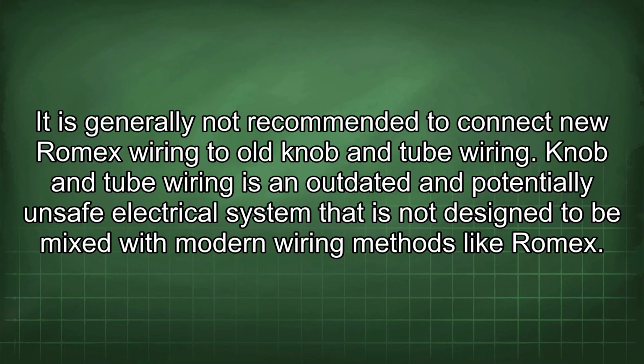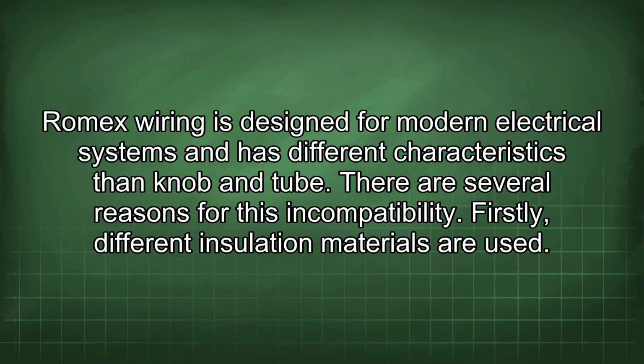It is generally not recommended to connect new Romex wiring to old knob and tube wiring. Knob and tube wiring is an outdated and potentially unsafe electrical system that is not designed to be mixed with modern wiring methods like Romex. Romex wiring is designed for modern electrical systems and has different characteristics than knob and tube. There are several reasons for this incompatibility.